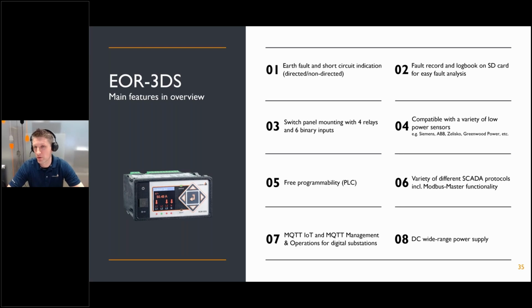We can, of course, connect low power sensors of a lot of different manufacturers, not only sensors with 2-wire connection, but also sensors, especially from Siemens and ABB with RJ45 connector. We have PLC functionality on board. We have a really wide variety of different SCADA protocols, including this Modbus master functionality that goes in the direction of an SCADA gateway. We have 2 protocols based on MQTT, so for a cloud application and for remote maintenance of the device that we will see in the 5th chapter now.